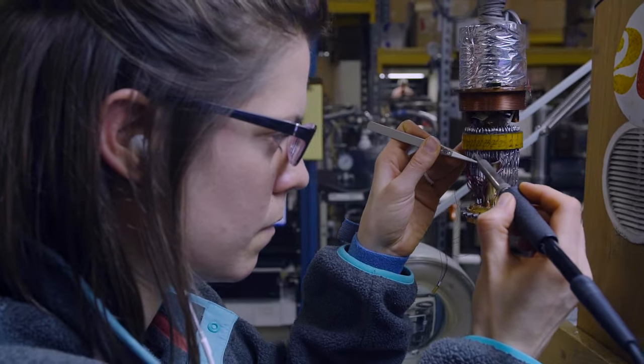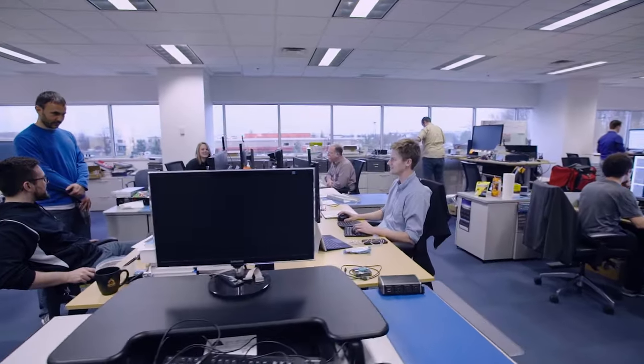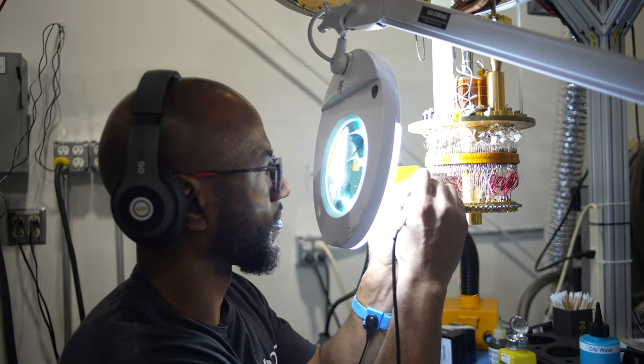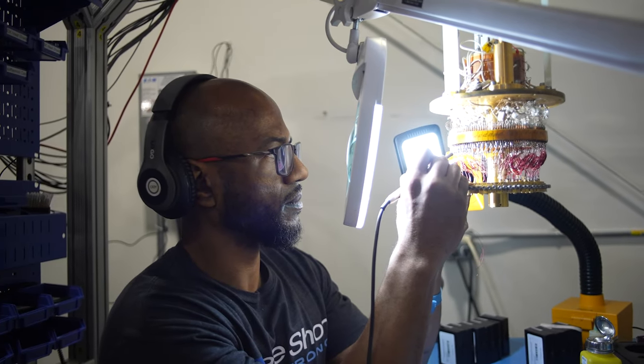Lakeshore temperature sensors are really unique in the world in that beyond just the physical sensor itself, we have a lot of support infrastructure around that sensor to make it truly something amazing. The sensor itself is stable, reliable, and purpose-built for cryogenic applications, but the calibration of that sensor — the knowledge of how the temperature scale maps to that physical property — that's what makes it really valuable. We have a world-class calibration facility with a truly staggering number of traceable secondary standards that we use to map the temperature scale onto those sensors, so that when you get a sensor you can truly trust the measurements you're getting from it.